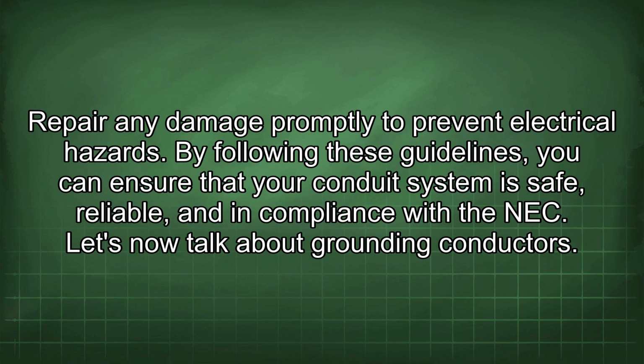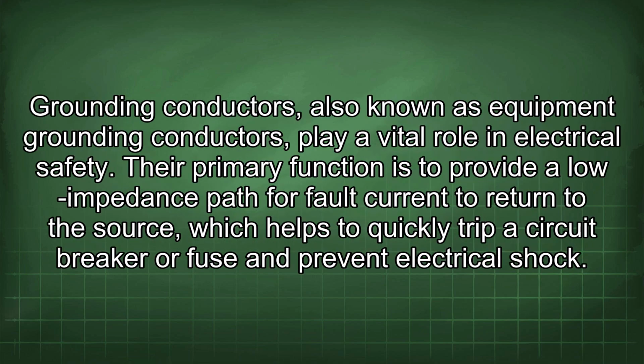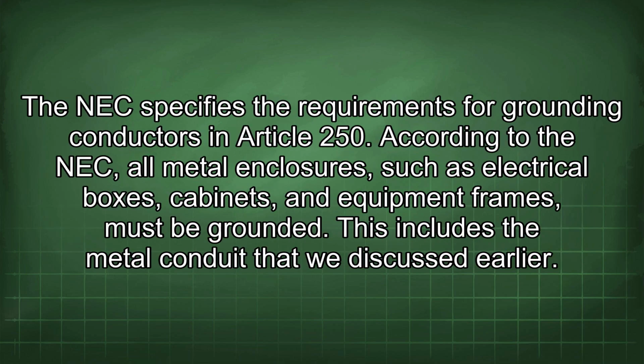Let's now talk about grounding conductors. Grounding conductors, also known as equipment grounding conductors, play a vital role in electrical safety. Their primary function is to provide a low impedance path for fault current to return to the source, which helps to quickly trip a circuit breaker or fuse and prevent electrical shock. The NEC specifies the requirements for grounding conductors in Article 250.